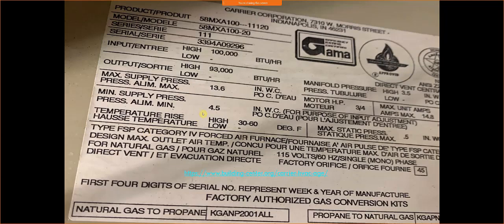The other information on here is also vital. It's going to tell me my gas pressure, my temperature rise, and that's basically the temperature going into the furnace and the temperature coming out. So if I have a 70-degree temperature going into the furnace via my return, I should have 100 to 130 degrees coming out of my furnace above the coil, about 12 to 18 inches above it if I have it. If I'm outside those parameters, I need to adjust the system. Over here is my static pressure, motor horsepower, amps, that sort of thing.